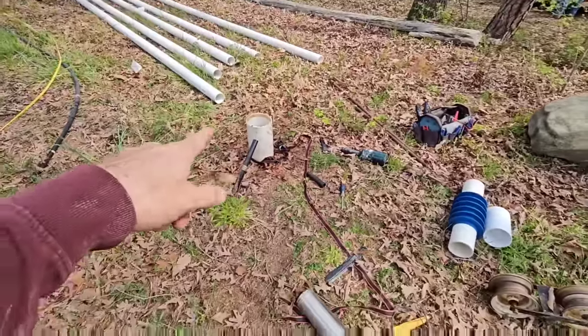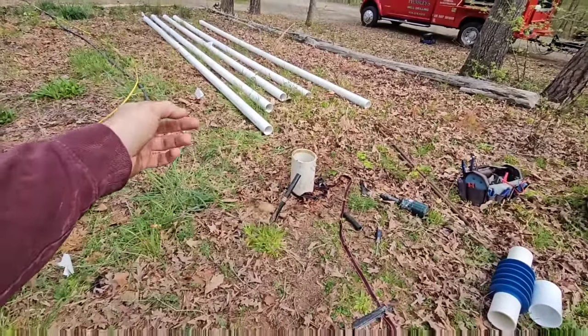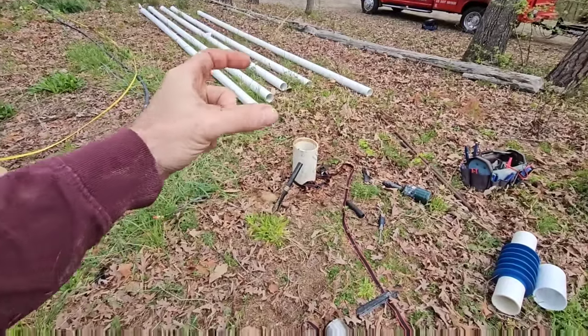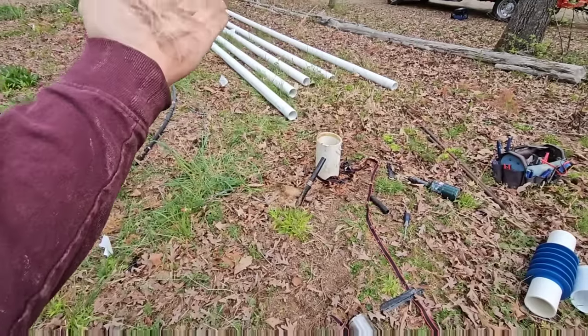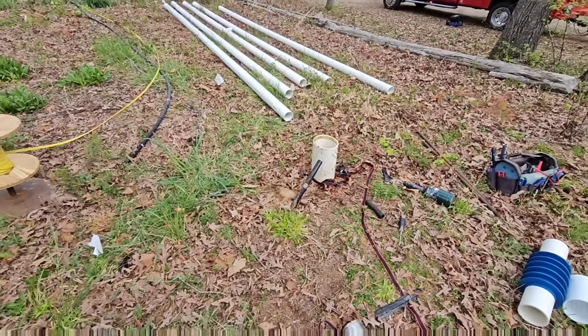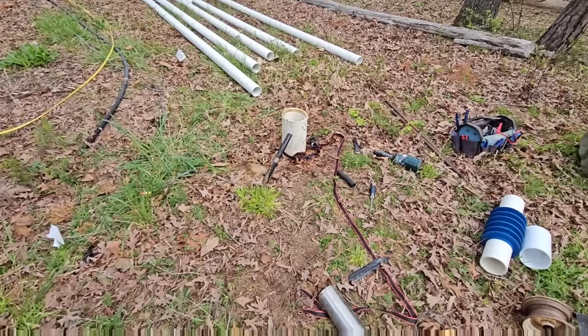When we install the pump back in the well and we put it all in, I'm going to run water to get the well to run clean, right? Yeah. So I'm going to hook up a valve and a pressure gauge in front of it. And I'm going to close the valve and see if it builds up to like 140 PSI. Because if it does, then we'll know the pump's good. Right. If I close the valve and it only builds up like 65 PSI, pump's bad.